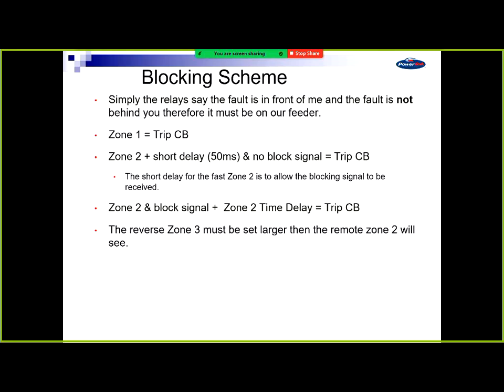We don't actually send a signal at that time for a feeder fault. We only send signals when the faults are behind us and not on our feeder. So we reduce the risk that the signal won't get through the faulted phase. Now, we did use permissive signalling on PLC, and I don't know the statistics of how many times they didn't get through, but it wasn't that bad. It's not that it's bad, it's just that wanting to mitigate your risk, change to a blocking scheme, you mitigate your risk at no real cost. Well, it's no cost, you just have to design a little bit of extra work.